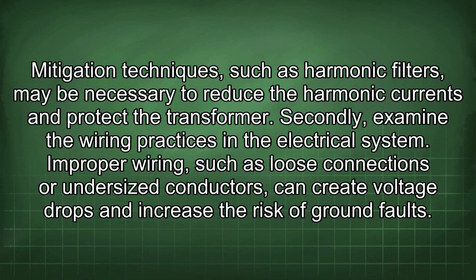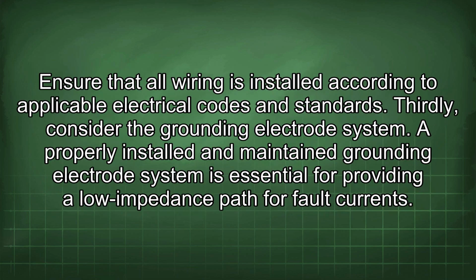Mitigation techniques such as harmonic filters may be necessary to reduce the harmonic currents and protect the transformer. Secondly, examine the wiring practices in the electrical system. Improper wiring, such as loose connections or undersized conductors, can create voltage drops and increase the risk of ground faults. Ensure that all wiring is installed according to applicable electrical codes and standards.